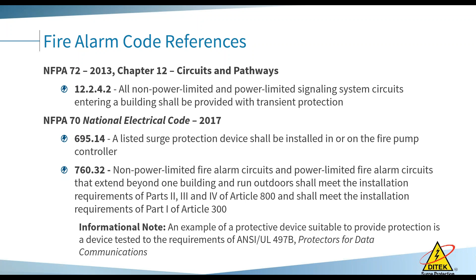And the one that I see forgotten a lot on a fire alarm system seems to be the PIV, which is attached to a big, huge metal pipe, whether it's out by the street or in a riser room. But a lot of times that one seems to get left out on surge protection. Of course, something's going to hop onto that and come right into your building because it's attached to the biggest metal pipe probably on the property. So just something to throw out there as I go through.